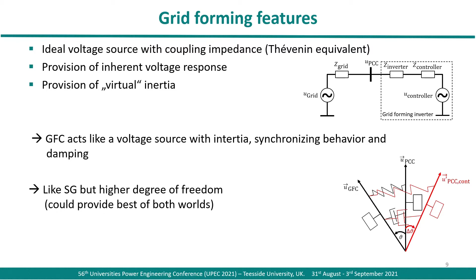Now, we will look at the behavior of a grid forming control. First set, the difference to a grid following control is just visible in the first few grid periods or in total absence of a synchronous generator. You are less likely to run an only PLL-based system, which is somehow normal for the grid following controls, in an islanded operation. Without additional control techniques, the grid frequency will drift apart. The main difference between both control methods will be visible after the PLL found the grid angle.